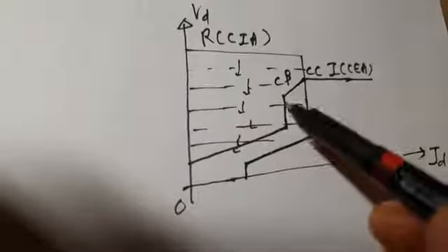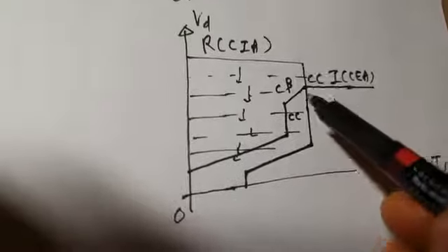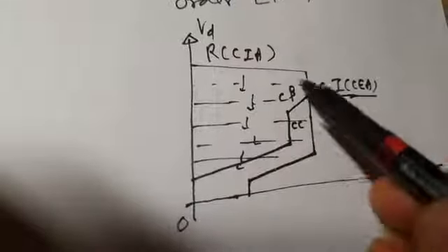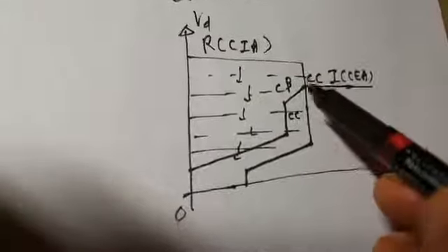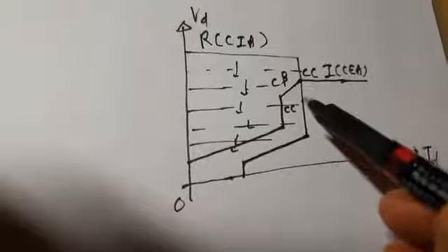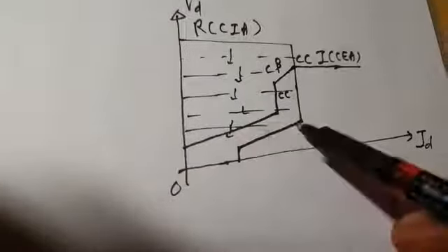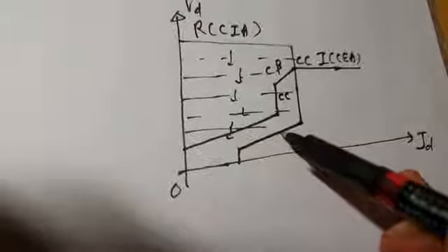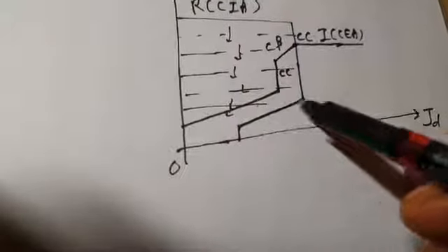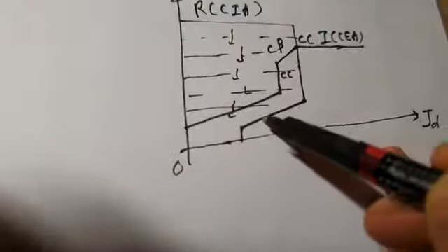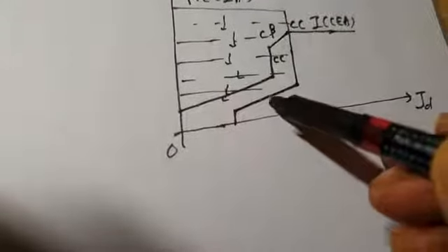You see here, this is the rectifier characteristic. Under normal operation, it tries to maintain the current constant, but under extremely low voltage conditions, it puts some limit on the current. So if your voltage goes on decreasing, the current does not stay very high.